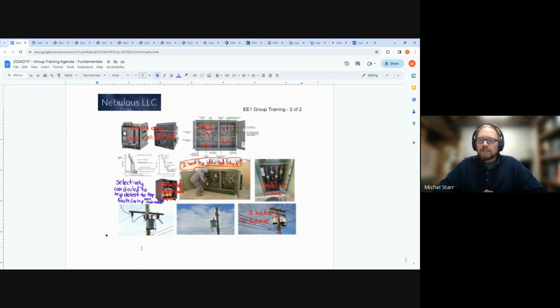That may not be the case if one phase is loaded more than the others. The electrical code wants you to balance those as best you can, within 10%, across phases A, B, and C, but you might have a phase that's hotter for that reason.